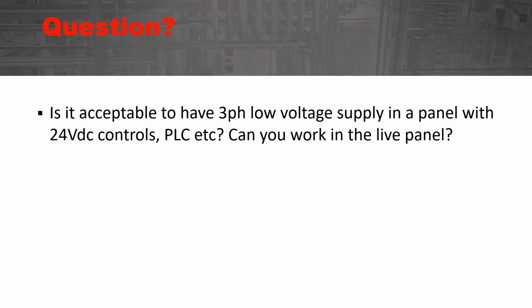Let me add a little bit to that, the 24 volt DC controls. And Bono's exactly right. They do have to be separated if they are class 1 or class 2. And for this, you go to the National Electrical Code, Article 725. It's a very interesting article. And it tells us about separating class 2 and class 3 from regular building wiring or class 1. As an electrician, I always thought that Article 725 was, quote, low voltage. Well, it's not. Class 1 can be up to 600 volts.